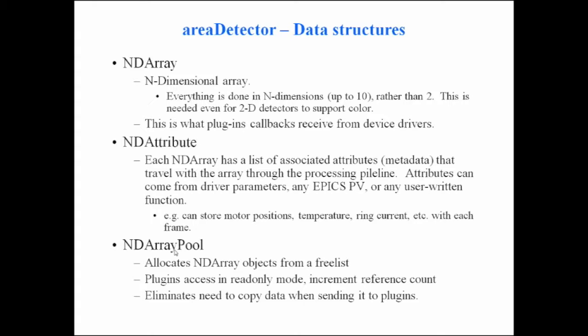There are a few data structures used in area detector that it helps to understand. The most important is an object called an NDArray — an N-dimensional array. One of the first talks on area detector here, Andrew Johnson suggested generalizing from a two-dimensional driver to N dimensions, which was pretty easy and opened up the capability of supporting things that are not just two-dimensional detectors.